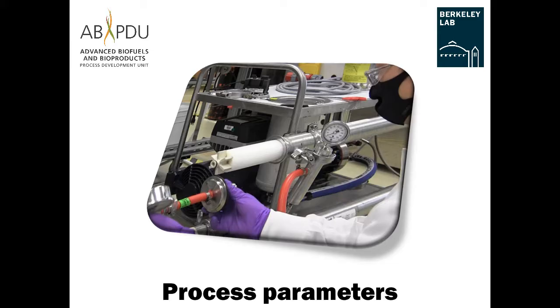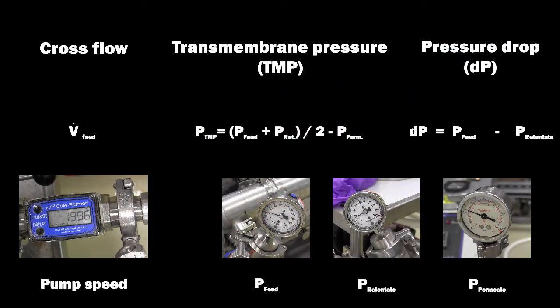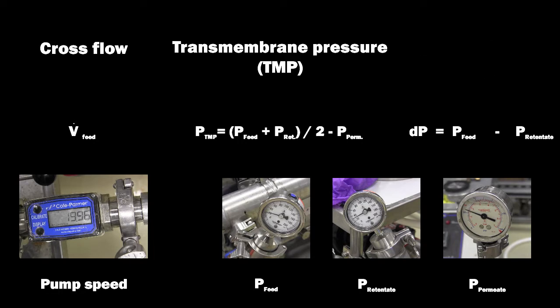The process parameters: Here we will give an overview of the key process parameters and controls involved with running the M20. The three key parameters are the feed cross flow rate, the transmembrane pressure or TMP, and the pressure drop or DP. It is critical that each parameter is operated within the range as specified in the membrane product documentation to ensure optimal process performance and to avoid process failure or damaging the membrane.